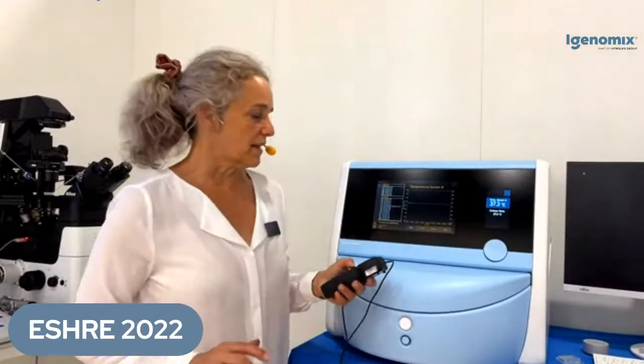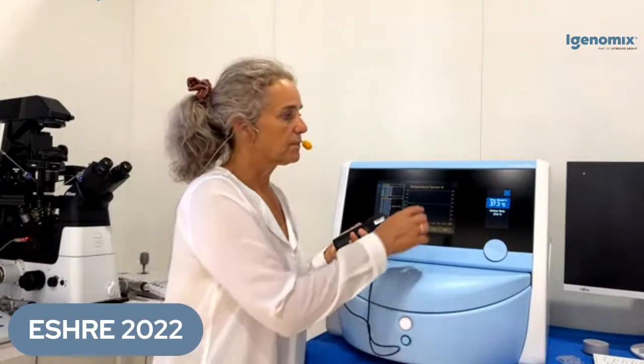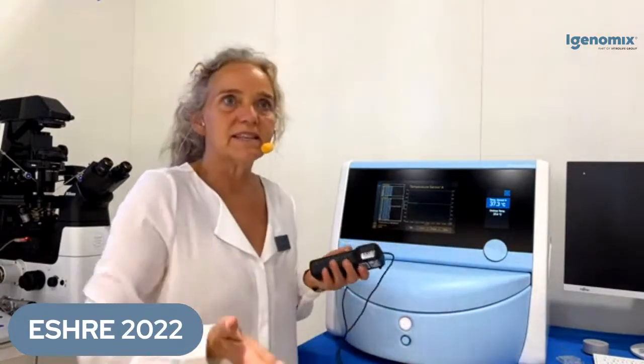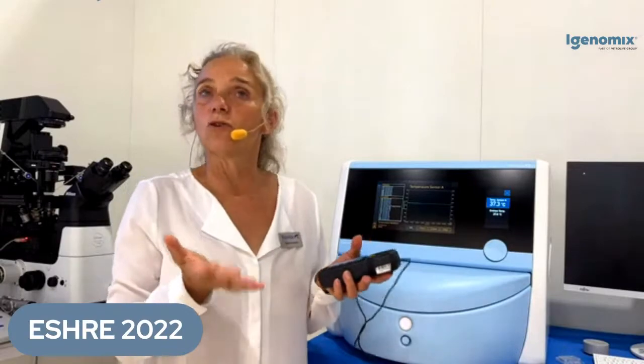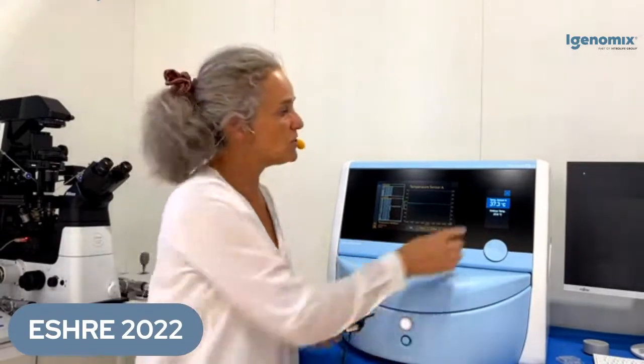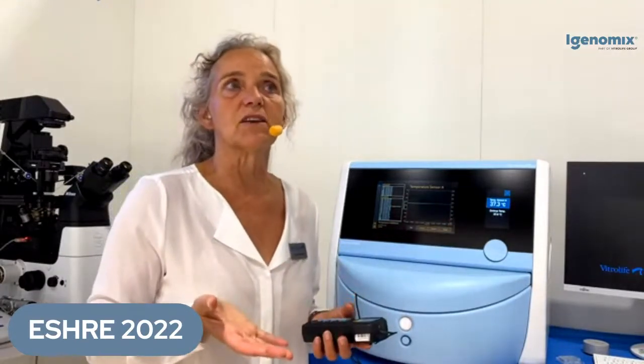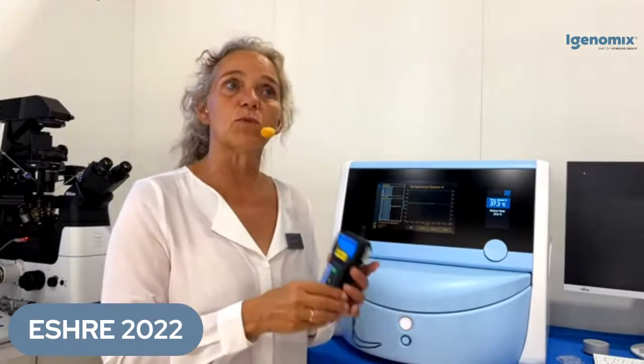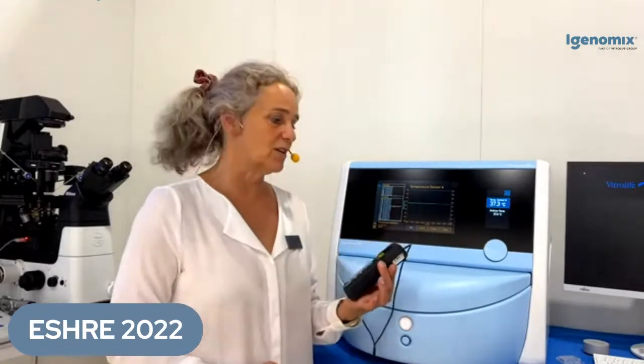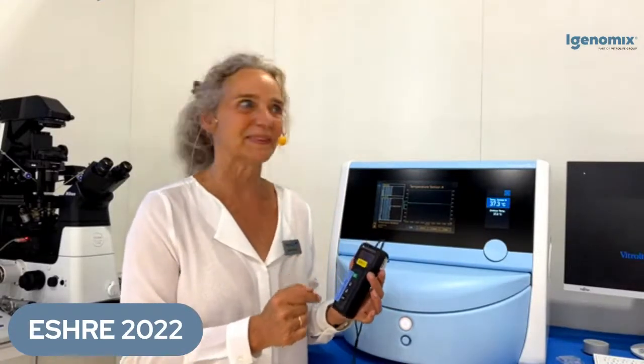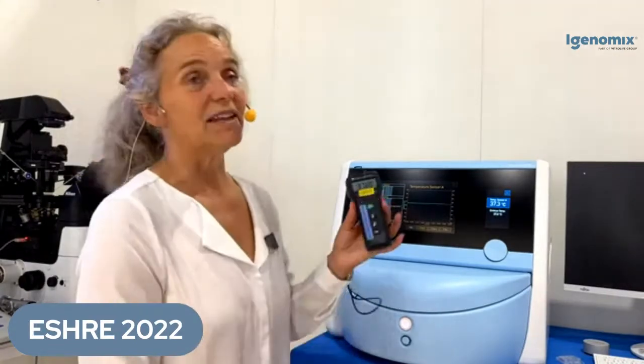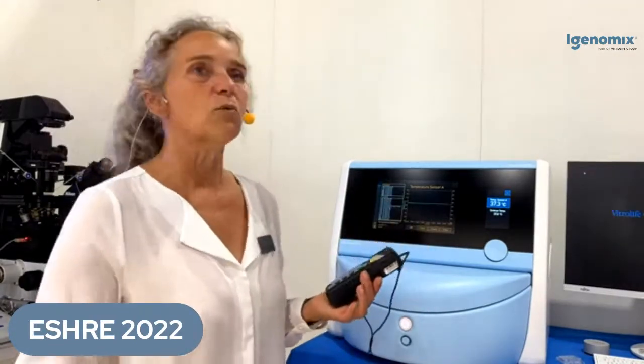What you should take into account here is that this rotating plate is heated up to 37.3 degrees to ensure 37 where the embryos are cultured. So there is an offset of plus 0.3 degree. It means that when I do my test here, it should measure 37.3 degrees. Okay, is that clear? Good. Now it's already 37.2. We should wait around 10 minutes before you read your measurement.